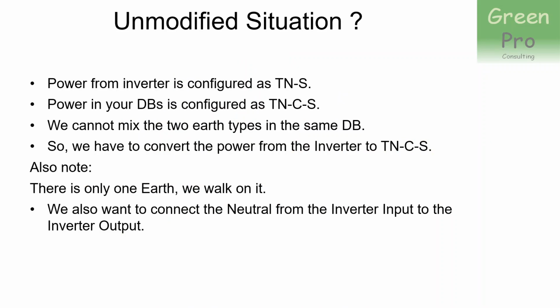So what is the unmodified situation? You're sitting with an inverter which is configured as a TNS earthing system. The power in your DB, from Eskom, from the street, from whatever, is configured as a TNCS earthing system. So we cannot mix the two earth types in the same DB. And now we have to convert TNS to TNCS. Then also note, there's only one earth, and that is the one that we walk on. So whatever you do, there's always a single earth.